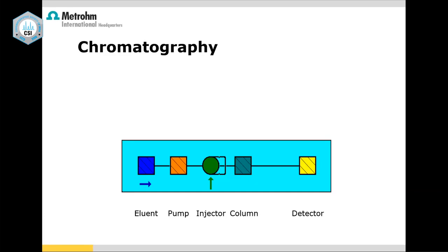So far you have probably come across the UV detector, fluorescence detector, diode array detectors, PDA, photodiode array, etc., RI or ELSD. And of course you have come across mass also. So here it's entirely different. Of course, you can use those detectors also, but here it is mainly the conductivity detector, because you're talking about ions, and ions will have conductivity. Let's go step by step.